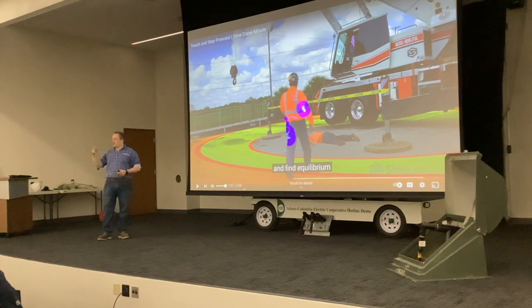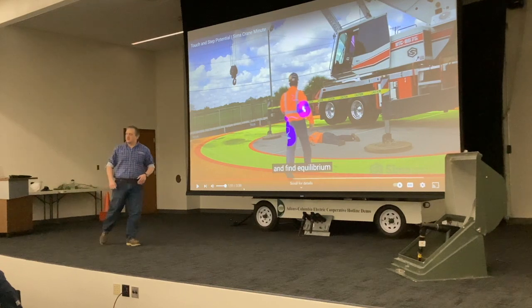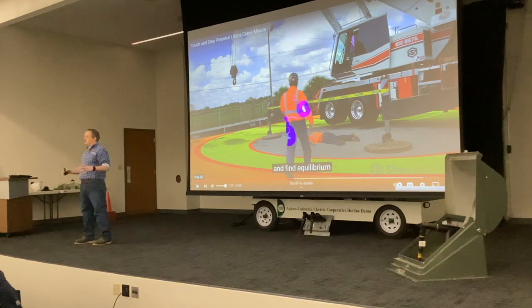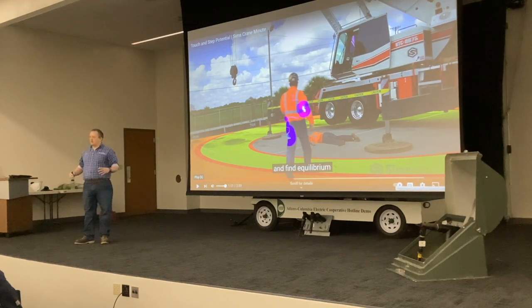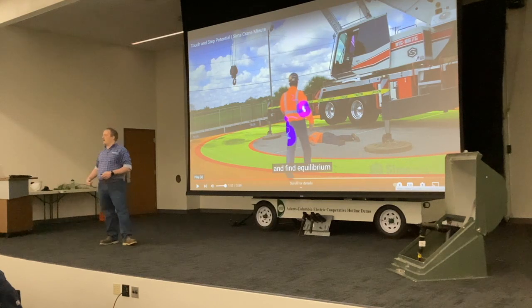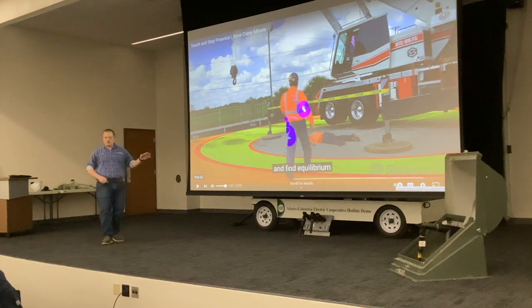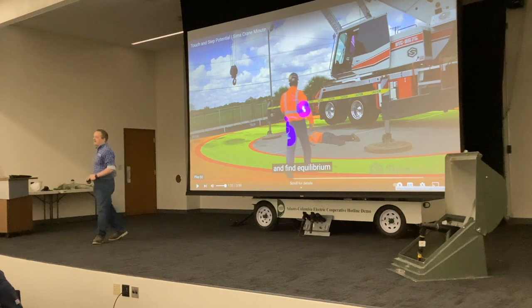So this is all theoretical numbers here because I'm bad at math and I'm not going to do the actual math. Say we had 5,000 volts going into the ground over there. And then I'm standing in 3,000 volts right now. If I took a step and I stepped into 4,000 volts, how many volts are going through my body? 1,000. So that's the idea of those rings of potential. You're walking through different voltage. When you bridge a gap between one voltage to the next, you become the conductor. And that difference goes through your body. And that's where that electrical shock would come from. Like I said, all those numbers are theoretical. I kept them really simple because I'm bad at math. All right, Ryan.